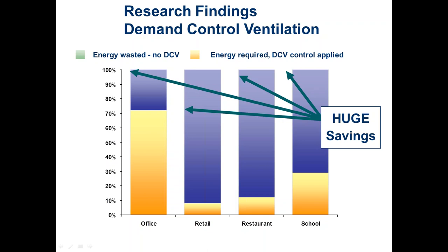Schools show about 70% savings, which might seem high, but each kid can only be in one room at a time. If the gym, library, lunchroom, and classrooms are all designed for 100% occupancy and systems run all day regardless, you're overventilating every unoccupied room. With CO2 sensors, you can shut off or modulate back ventilation when rooms are empty. Additionally, classrooms designed for 35 kids but only having 27 this year — no one rebalances the system for that. Typical return on investment is almost always under a year and a half.